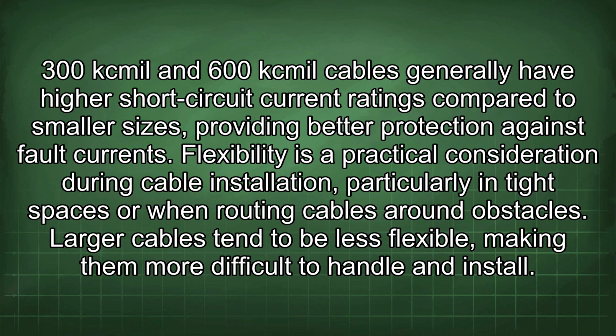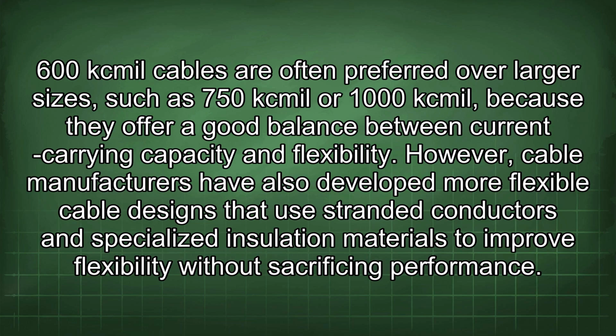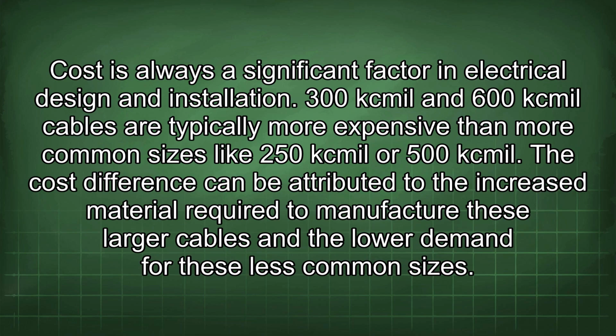Flexibility is a practical consideration during cable installation, particularly in tight spaces or when routing cables around obstacles. Larger cables tend to be less flexible, making them more difficult to handle and install. 600kcmil cables are often preferred over larger sizes, such as 750kcmil or 1000kcmil, because they offer a good balance between current carrying capacity and flexibility. However, cable manufacturers have also developed more flexible cable designs that use stranded conductors and specialized insulation materials to improve flexibility without sacrificing performance.